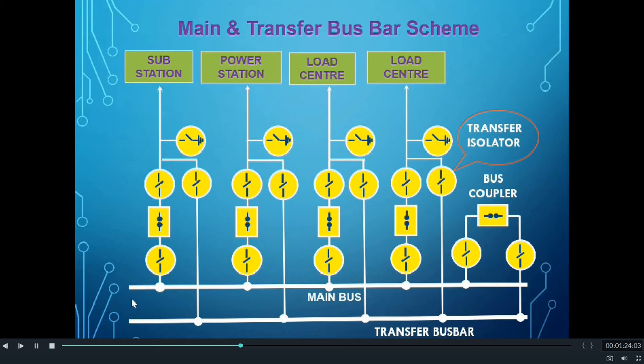In a Main and Transfer Busbar Scheme, the number of isolators used per feeder are 3, and one extra Busbar is used. Both the Busbars are connected to each other by a Bus coupler. The Bus coupler is a combination of a circuit breaker and isolators on either side of the circuit breaker.